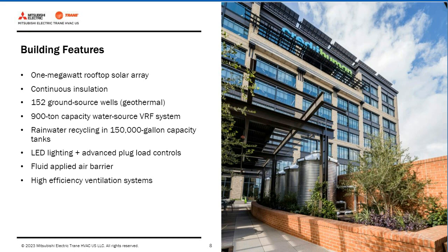The ground temperature is much more stable than air temperature, and for this reason, it is easier to maintain high COPs as you're delivering, in particular, heat to a larger building. So upfront costs are certainly higher for a well field, but again, when you're looking at longer ROIs being acceptable, it absolutely makes sense. I don't think I've mentioned yet that the target or design return on investment for this project was 12 to 13 years. At this rate, it's looking like it might, in actuality, be shorter than that. So we've got 152 geothermal wells.